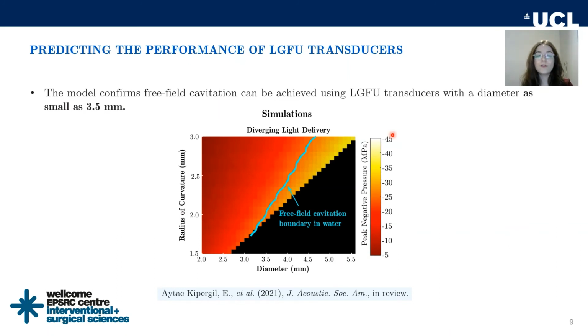Thanks to the computational efficiency of the simulation framework, we could explore various parameters including the radius of curvature and the diameter to predict the capabilities of LGFU transducers. We found that free field cavitation, which is an effect that could be used for ultrasound therapy, can be achieved using transducers with diameters as small as 3.5 mm, and transducers of that scale could be suitable to be integrated into interventional instruments.